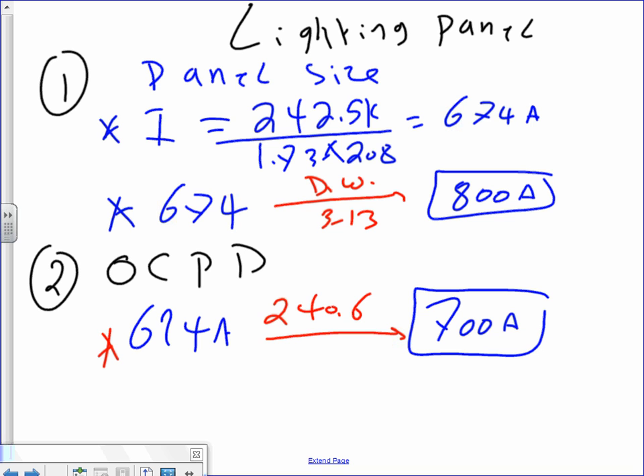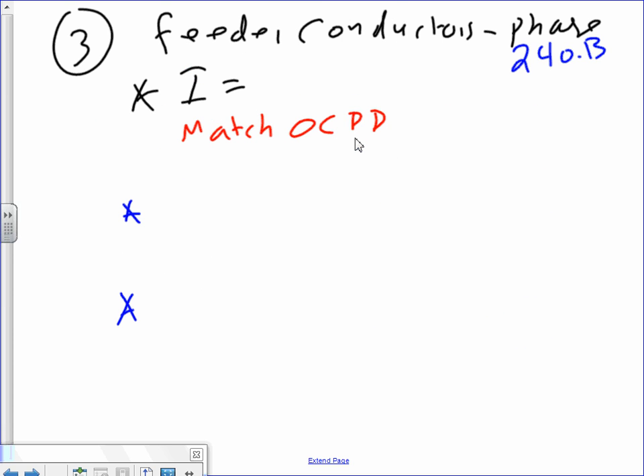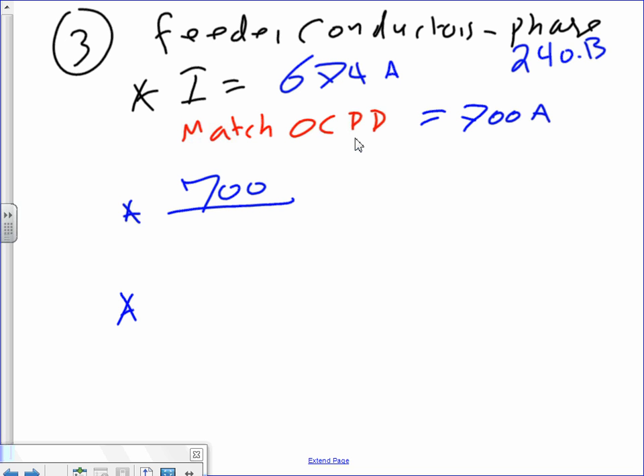All right, let's go size the cable. Am I going too fast? Now imagine if you had to write everything. That's why I give you that little cheat sheet, guys. Okay, lighting panel feeder. My feeder, guys, the size for the conductor: 674 amps. I always say engineers match the overcurrent protection device, which is 700 amp. Jay, do you think your table has a 700 amp cable? I guarantee you it doesn't.